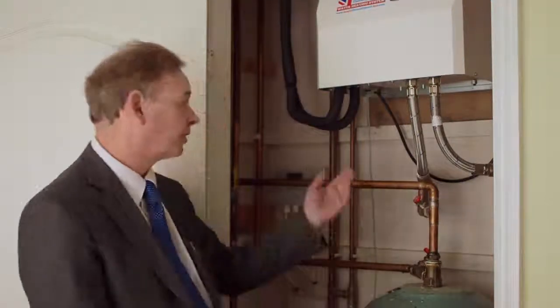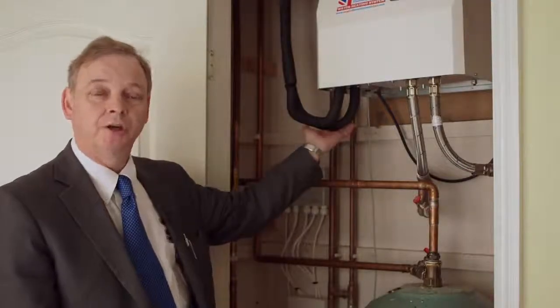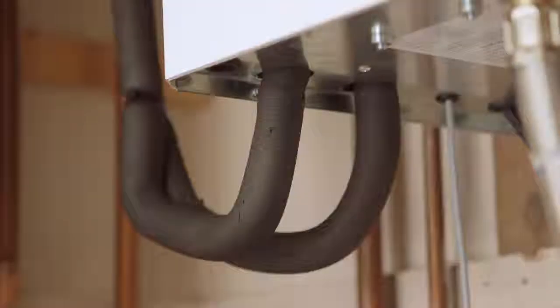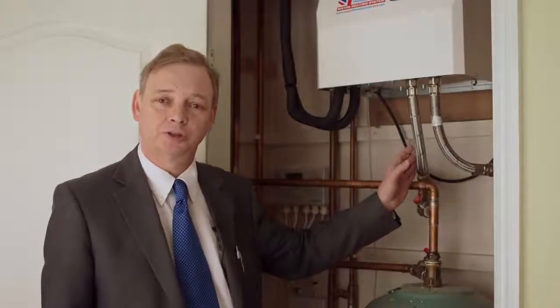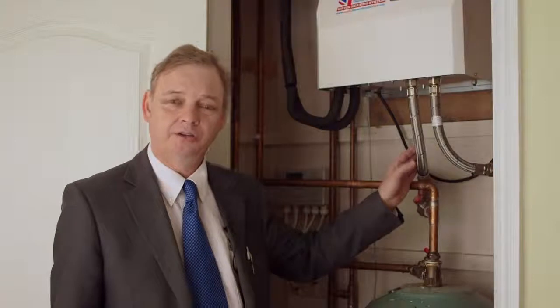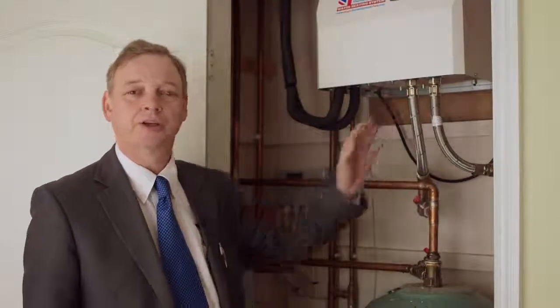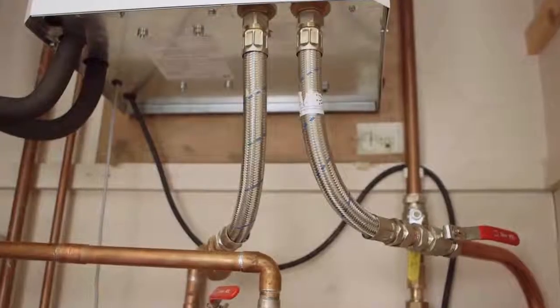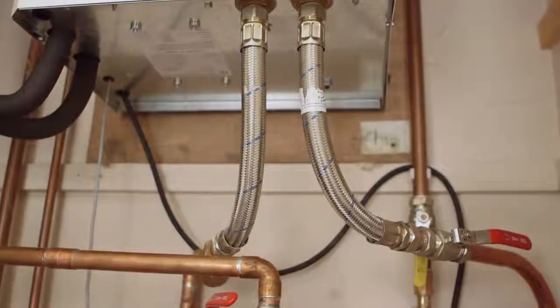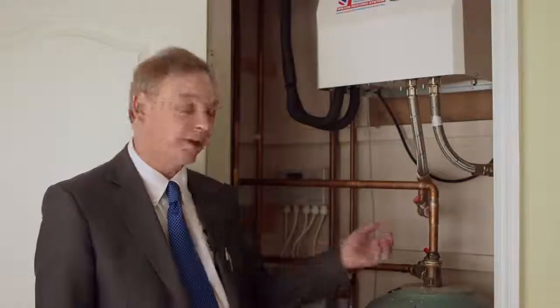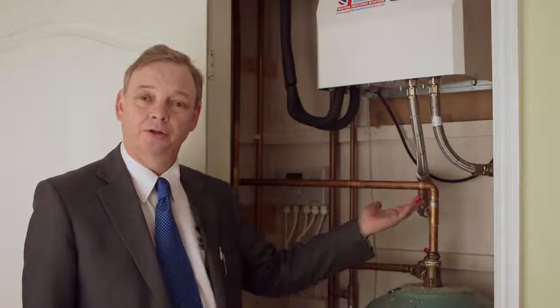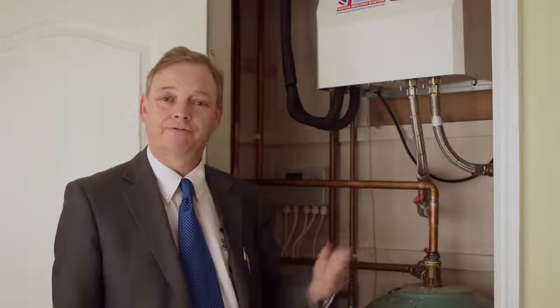I can now show you the system with all the components added. We start with the refrigeration piping with the flow and return, which link into service ports on the side of the box. We also have flexible hoses on the water circuit. This ensures that the box is isolated and vibration free. Also in the hydraulic circuit we have lever valves. That ensures that we can isolate the box from the water circuit.